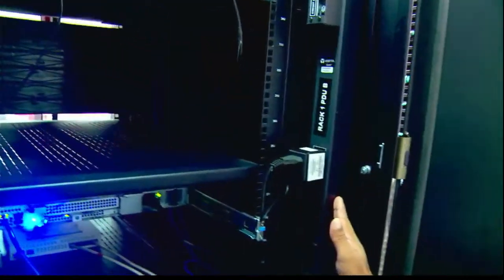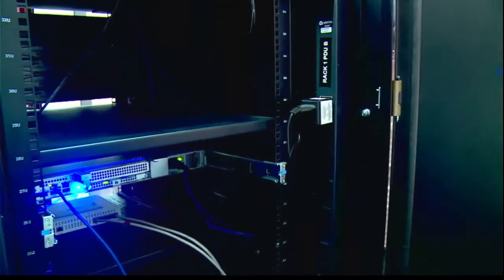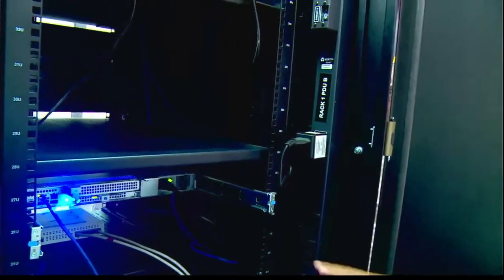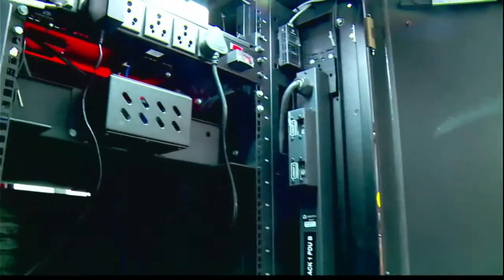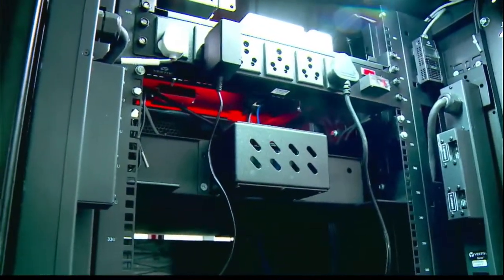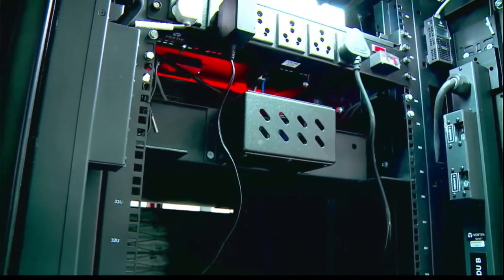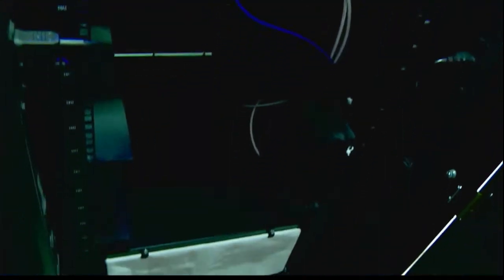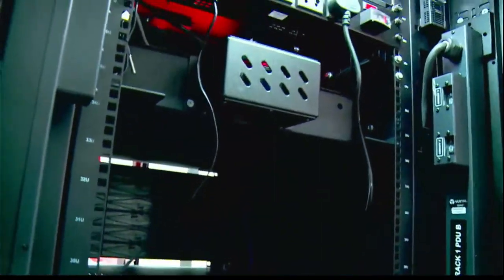Okay. This is your PDU, hot electrical distribution. This is your entire hot aisle, and everything is secure. Simple rack mount electrical distribution with breaker, required temperature sensors are there. So it will give you remotely also what is the airflow, what is the temperature, what is the humidity. There are two parts: one is physical access, which is fully secure, and another is tightly controlled cooling, which is ensured. 19-inch rail with all accessories to manage your IT infrastructure.